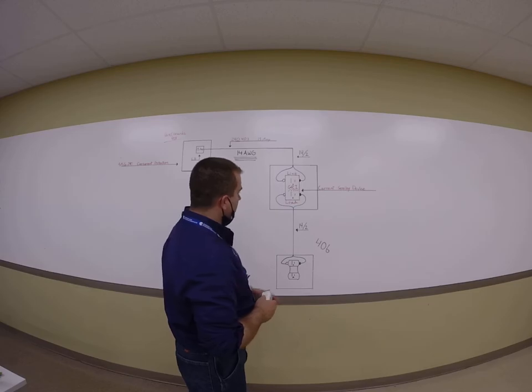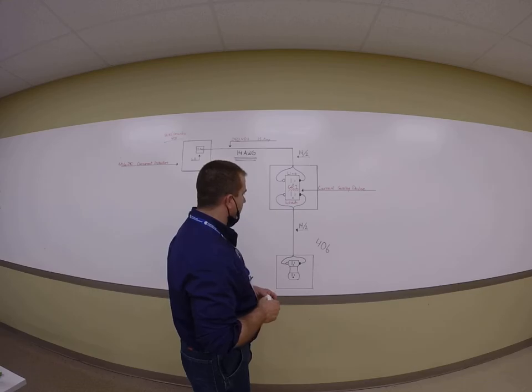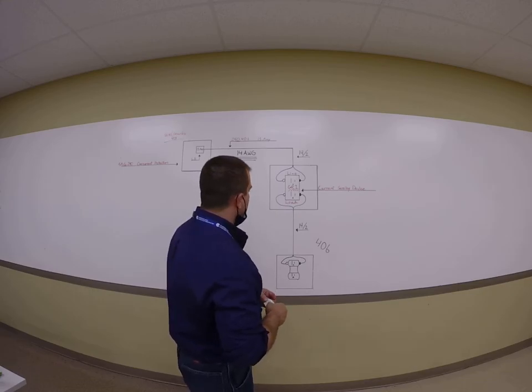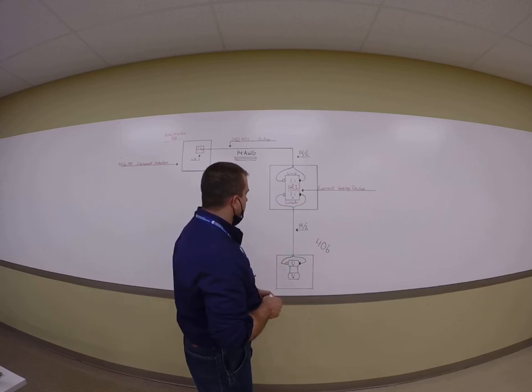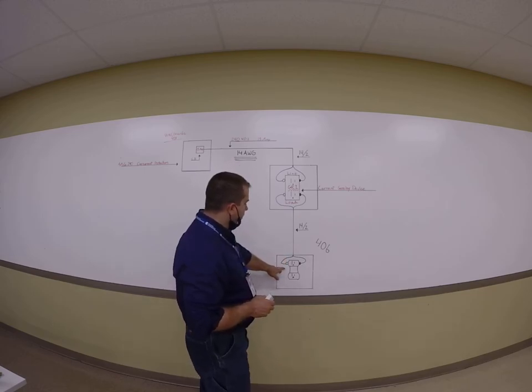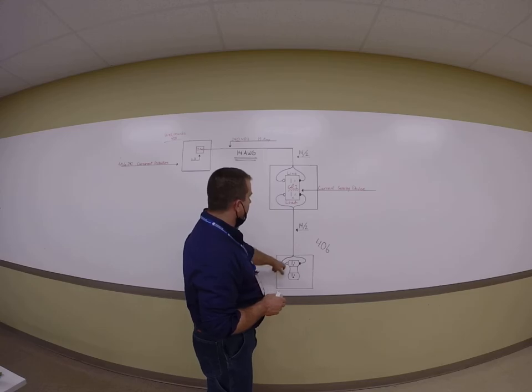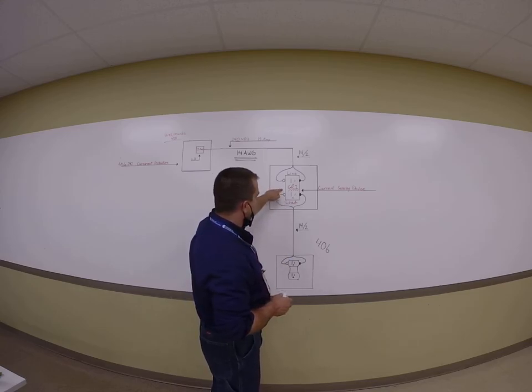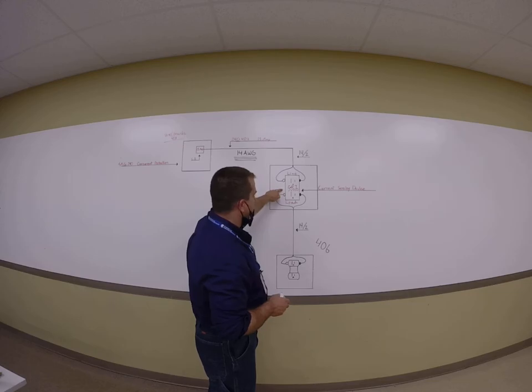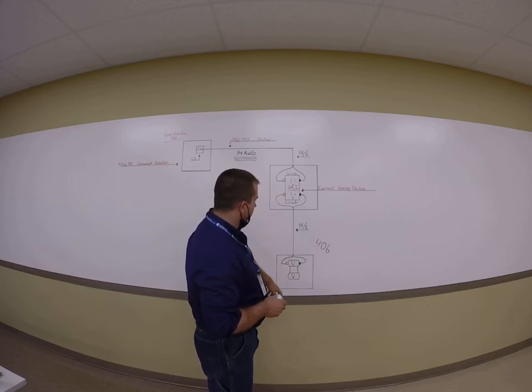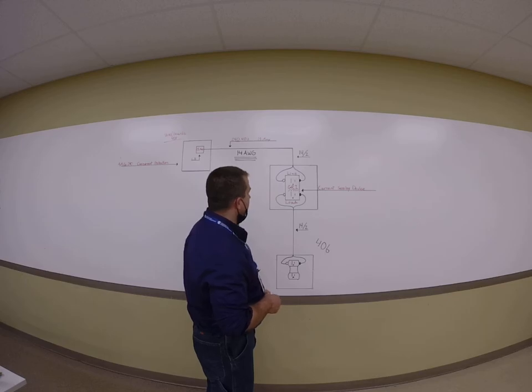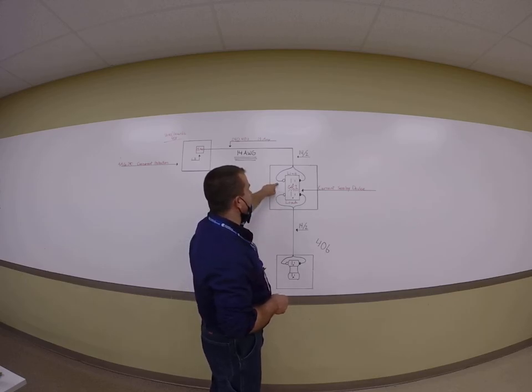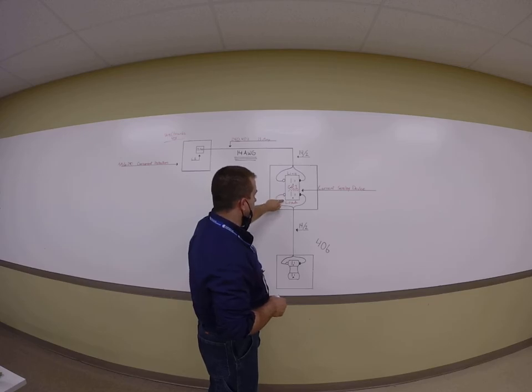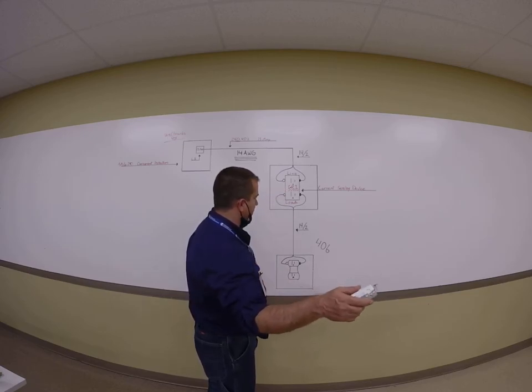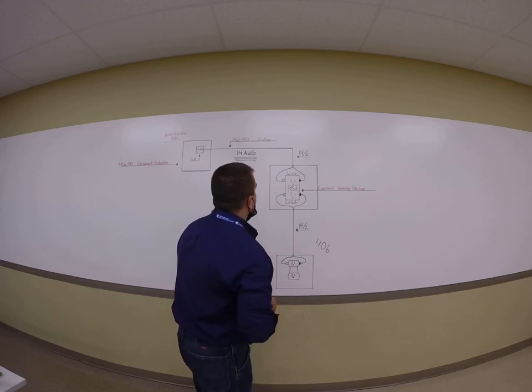That's more for code. To reiterate, which goes along with my video that I simulated with regular tap water versus distilled water, we have these at wet and damp locations. This $3 receptacle is now GFCI protected, and we only had to buy one $15 to $20 GFCI receptacle. And now I can have any amount of these on the load side of that and be protected. And the feed goes to the line. Line stands for feed. Load is anything that leaves beyond that point that you're trying to control or energize.